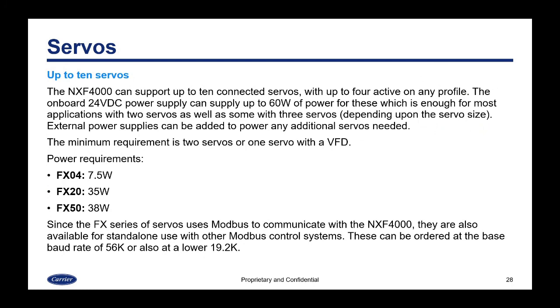The NXF4000 can support up to 10 connected servos with up to 4 active on any profile. The onboard 24 volt power supply can supply up to 60 watts of power, as I mentioned, which is enough for most applications with 2 servos, as well as some applications with 3 servos depending upon the servo size. External power supplies can also be added to power any additional servos needed. The minimum requirement is that you have 2 servos or 1 servo with a VFD.